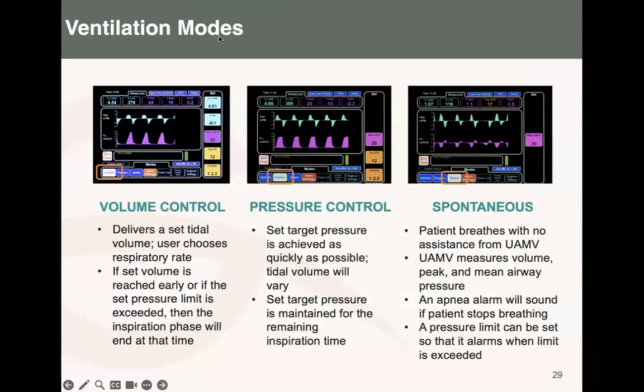So this is to remind ourselves of the capacity of the vent. I think all of you went through this during the training, but just to remind you, the machine can do volume control, where you just set the volume and the machine will deliver it. That's why you have to make sure you set the volume according to the weight, and of course the age is also considered. But I think you all know the range of the tidal volume. And actually, we do advise you to go to the lower side. You know the range comes from 5 to 10, but I think using 7, 6 is always okay.